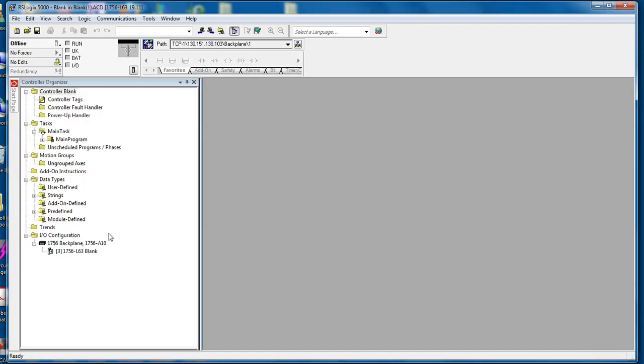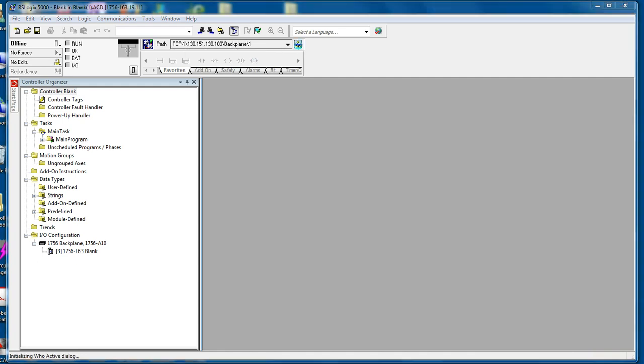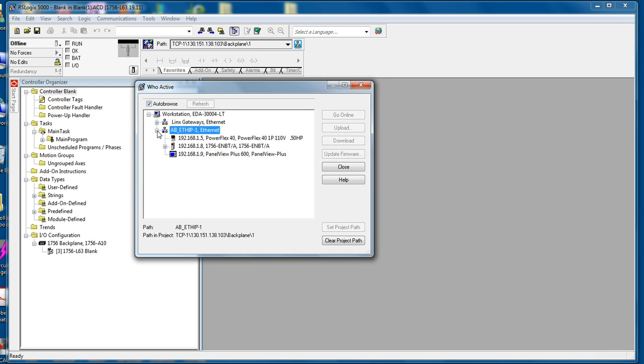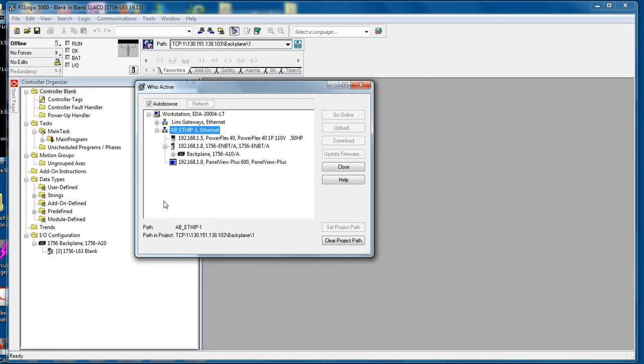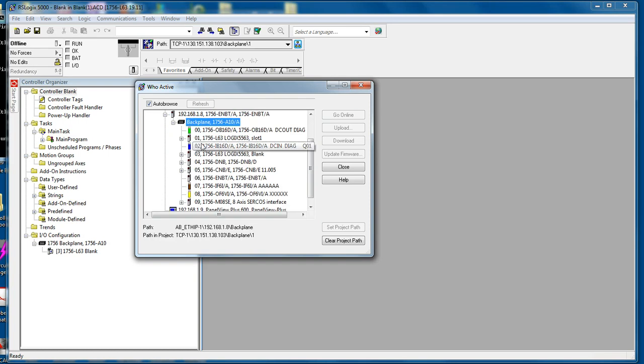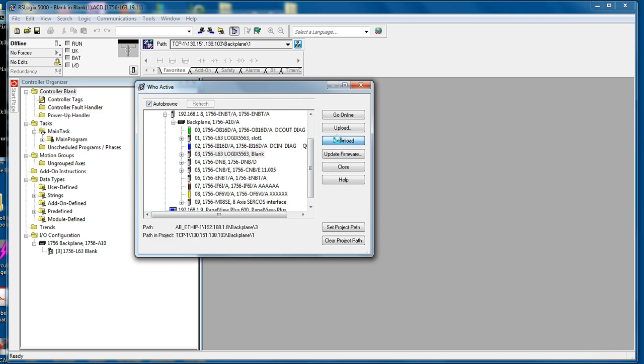So now that the file has been opened, you see on the I.O. configuration there's only one processor listed. So within the RS Who, change the path so you can navigate to the processor through the Ethernet IP card to the backplane. Here are Who active windows open. Click the plus sign next to your Ethernet IP driver through the backplane.